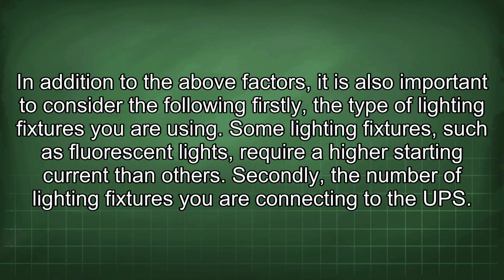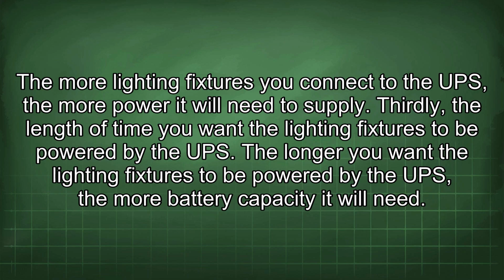In addition to the above factors, it is also important to consider the following. Firstly, the type of lighting fixtures you are using. Some lighting fixtures, such as fluorescent lights, require a higher starting current than others. Secondly, the number of lighting fixtures you are connecting to the UPS. The more lighting fixtures you connect to the UPS, the more power it will need to supply. Thirdly, the length of time you want the lighting fixtures to be powered by the UPS. The longer you want the lighting fixtures to be powered by the UPS, the more battery capacity it will need.